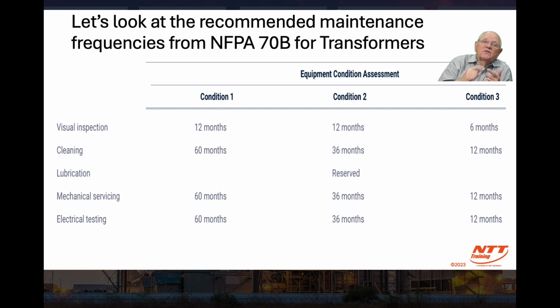We determine its physical condition, its criticality, its operating environment, and take the highest of the numbers, 1, 2, or 3. We take that to our table for equipment condition assessment to determine how often we perform maintenance on the equipment.